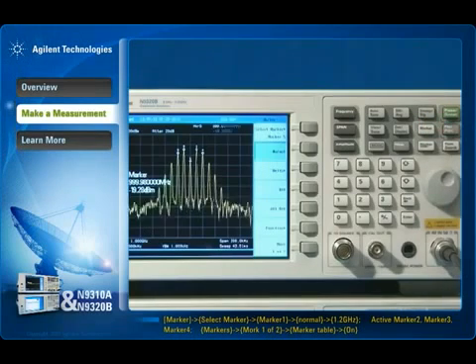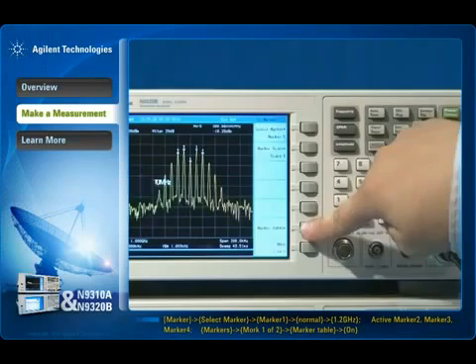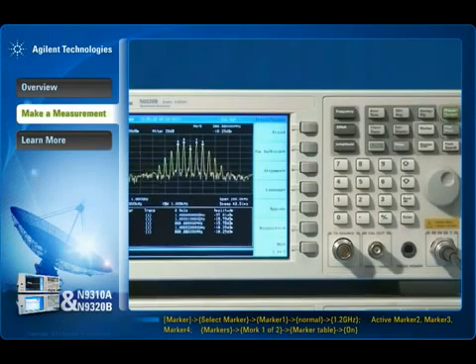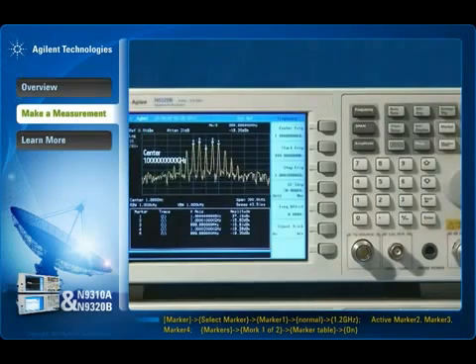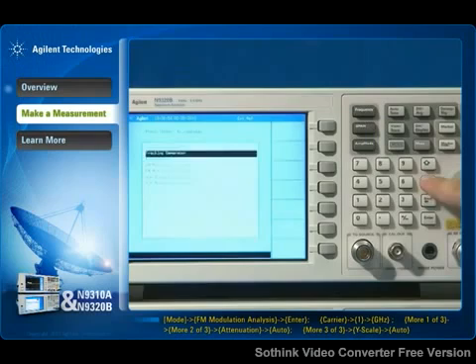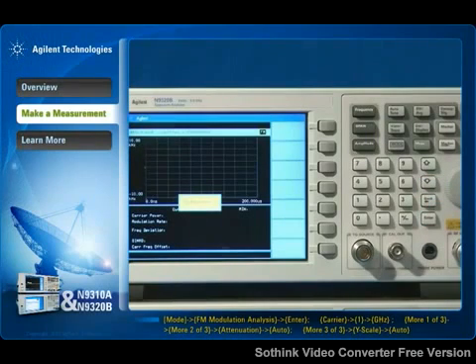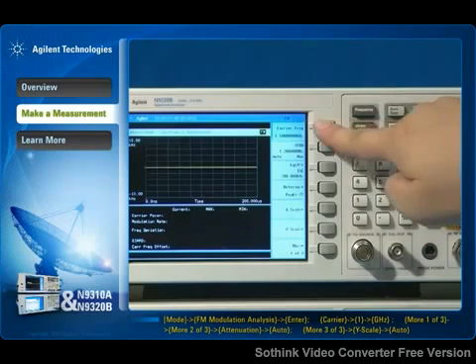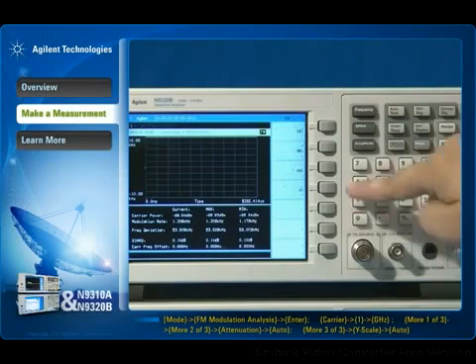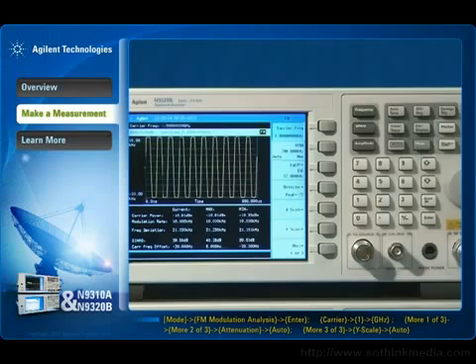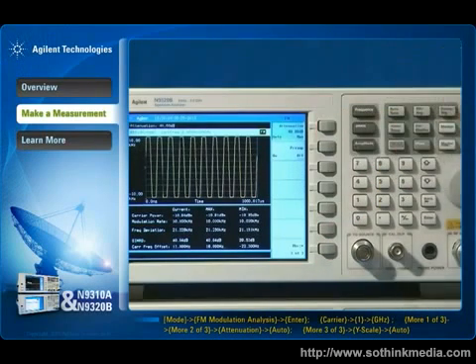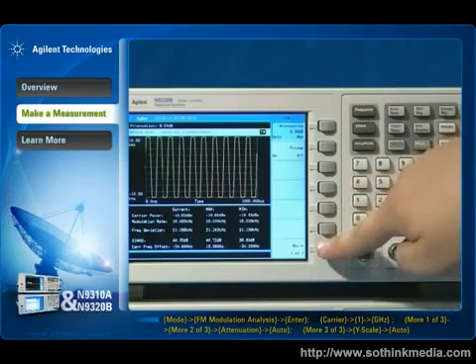You can use the marker table to list the frequency points of interest. If you want to better understand your analog signal, the N9320B option AMA provides the AM and FM demodulation metrics, including carrier power, modulation rate, AM depth, FM deviation, SINAD, and carrier frequency offset.